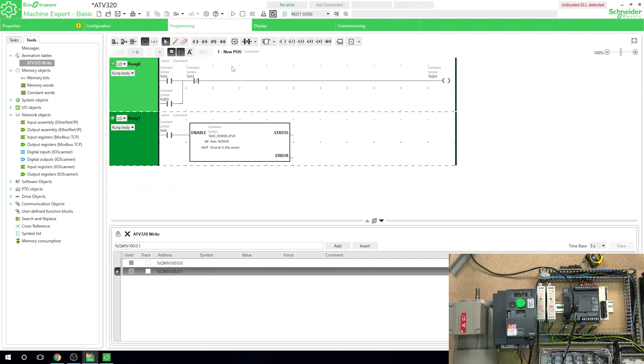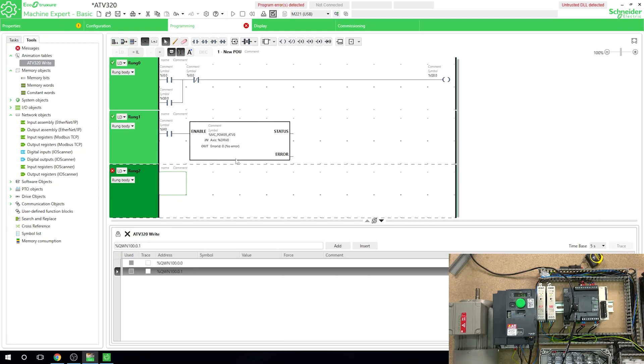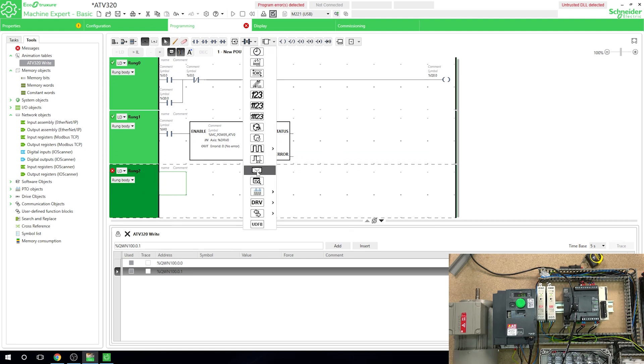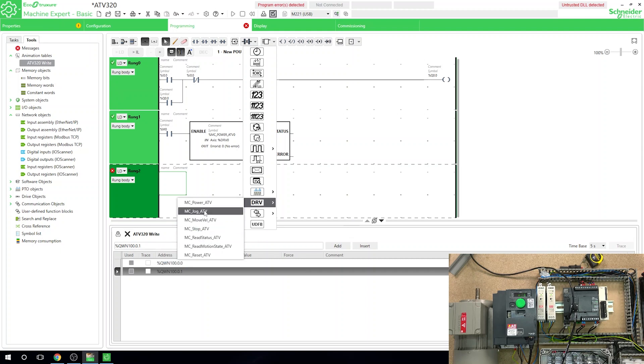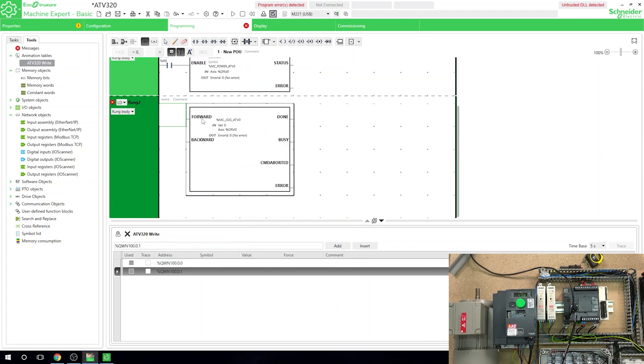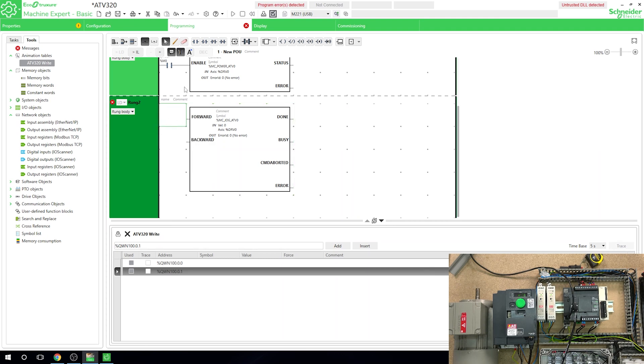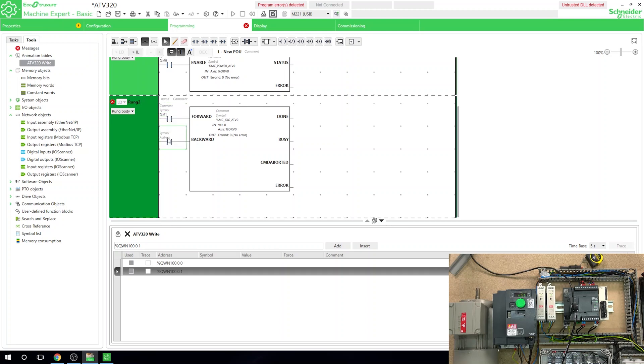Let's create another rung for the drive to go forward or reverse. Go into the drive function blocks and find the Jog block — you can see it has forwards and backwards. The drive object is already there. We're going to add a couple of addresses: one for forward and one for reverse, making them internal addresses. Forward will be M1 and reverse will be M2. These two bits will allow the drive to go forward or reverse.